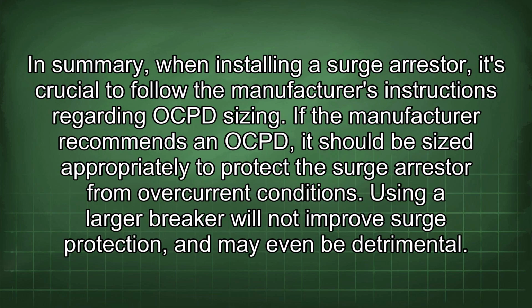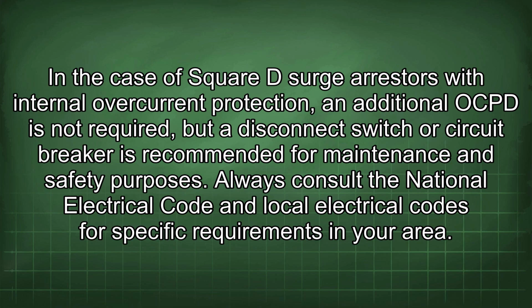In summary, when installing a surge arrestor, it's crucial to follow the manufacturer's instructions regarding OCPD sizing. If the manufacturer recommends an OCPD, it should be sized appropriately to protect the surge arrestor from overcurrent conditions. Using a larger breaker will not improve surge protection, and may even be detrimental. In the case of Square D surge arrestors with internal overcurrent protection, an additional OCPD is not required, but a disconnect switch or circuit breaker is recommended for maintenance and safety purposes.